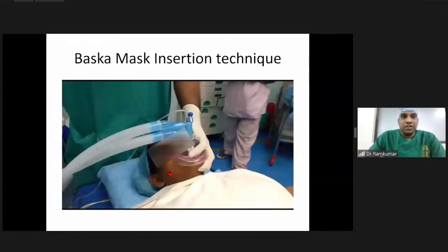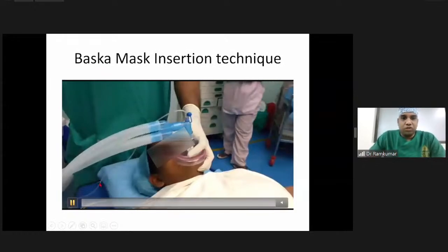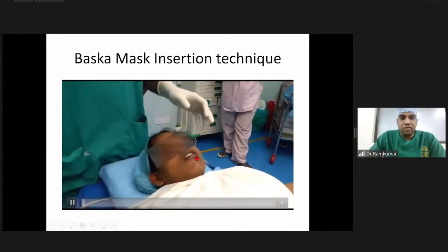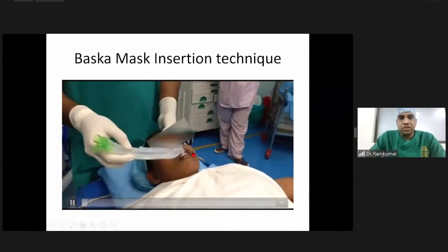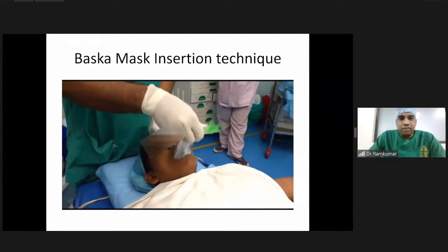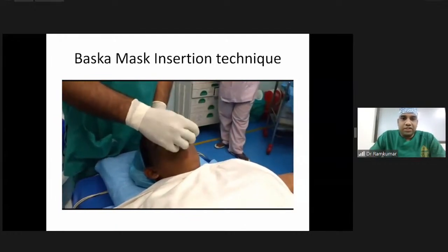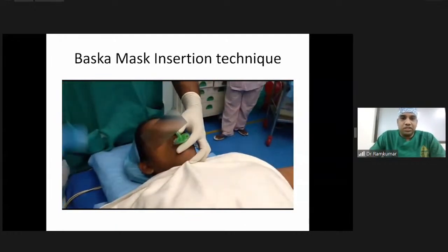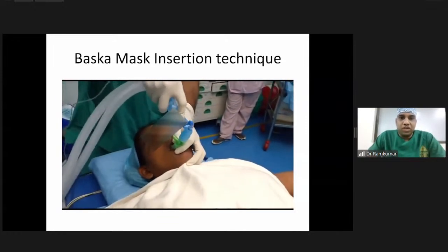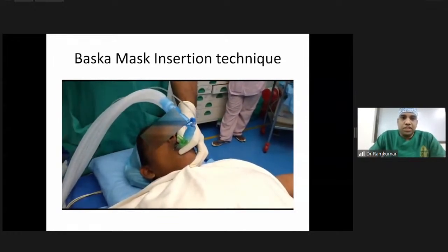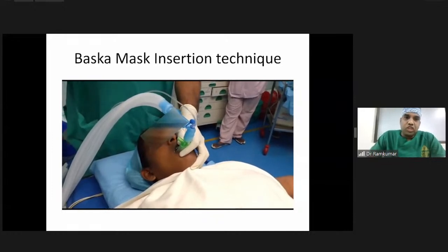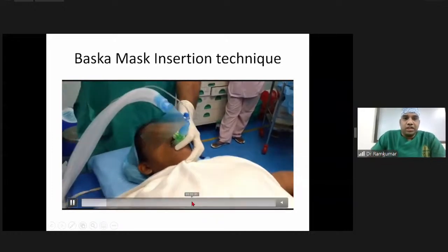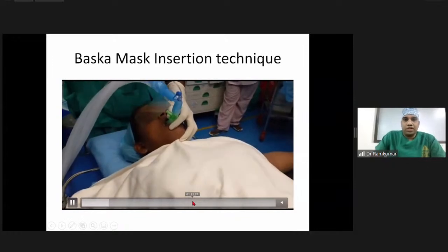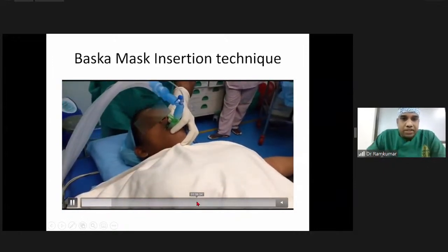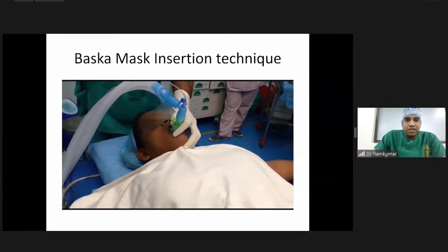Coming to the other device, the Baska mask, insertion is quite different. Here the device is lubricated on either surface with a water-based jelly, and the lip is also lubricated. The device is quite bulky, but this is how it's inserted. You get a very good sniffing position, and it is just inserted because it's a soft silicone tube. It smoothly squeezes itself into the hypopharynx, so it doesn't require any distal manual mouth opening or a distal insertion technique. So we can insert it within a few seconds, less than 10 seconds.